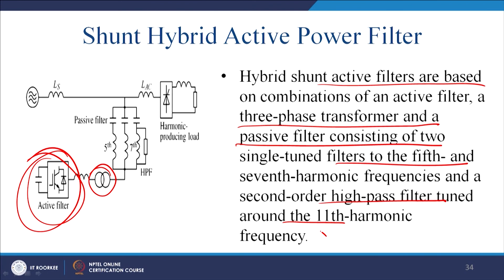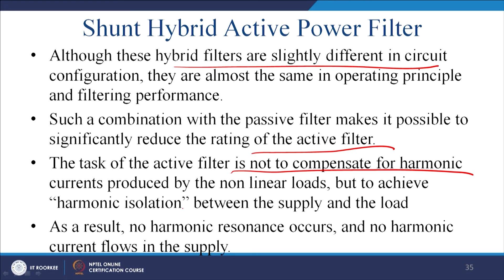So, although these hybrid filters are slightly different, and we have to understand the complexity of their different circuit configurations, they have almost the same operating principles as passive filtering. Just the combination with the passive filter makes it possible to significantly reduce the rating of the active filter, which is also sometimes a challenge. The task of the active filter is not only to compensate for the harmonic current produced by the nonlinear load, but also to achieve harmonic isolation between the supply and the load. As a result, no harmonic resonance occurs, no harmonic source current flows to the supply, and thus it damps out the harmonic oscillations.